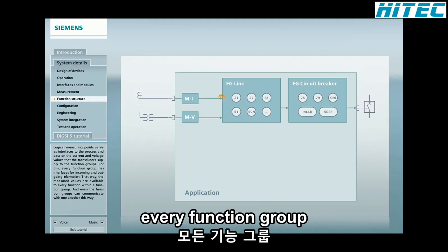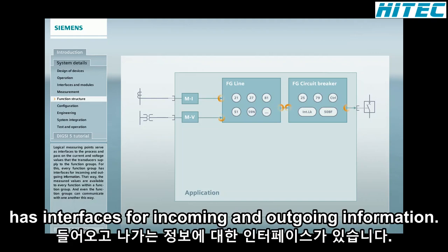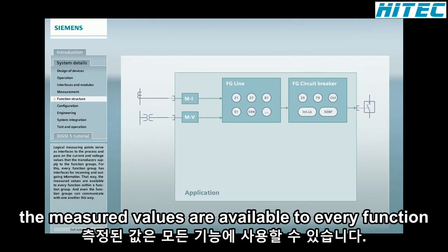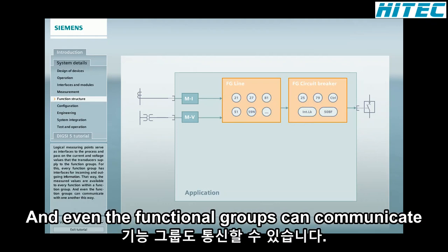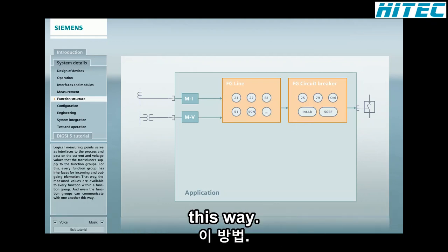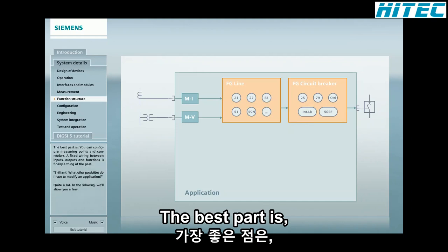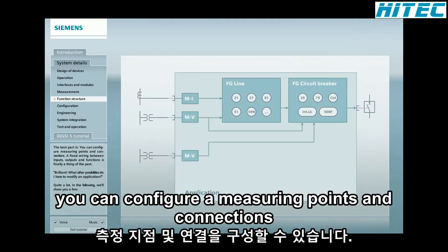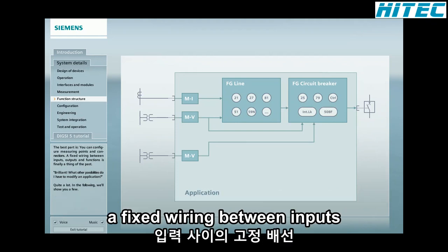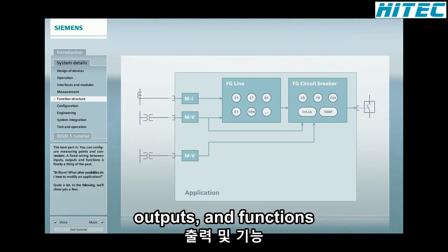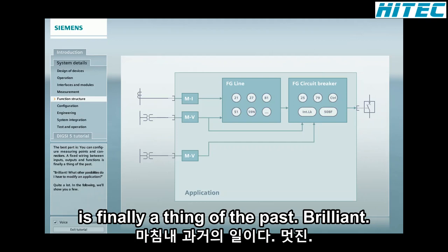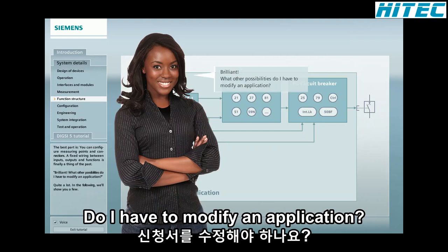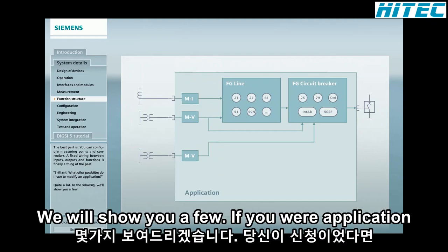For this, every function group has interfaces for incoming and outgoing information. That way, the measured values are available to every function within a function group, and even the function groups can communicate with one another this way. The best part is, you can configure measuring points and connections. A fixed wiring between inputs, outputs, and functions is finally a thing of the past. Brilliant! What other possibilities do I have to modify an application? Quite a lot. In the following, we will show you a few.